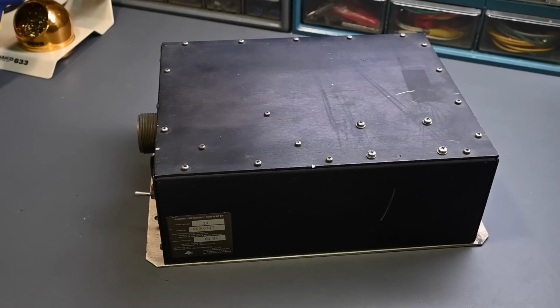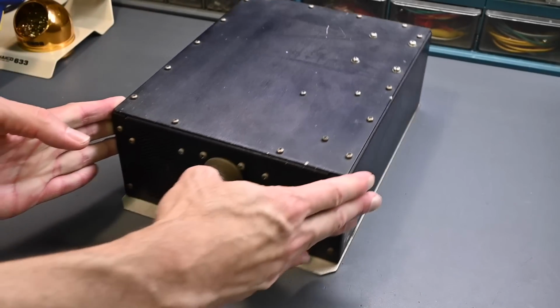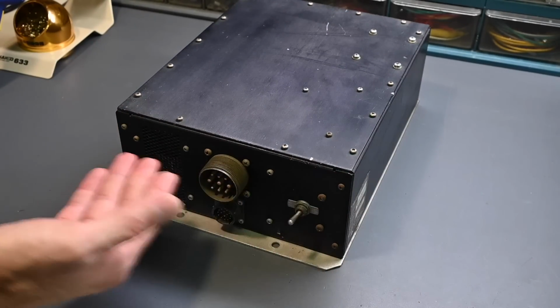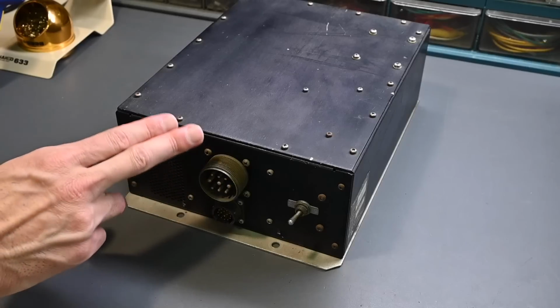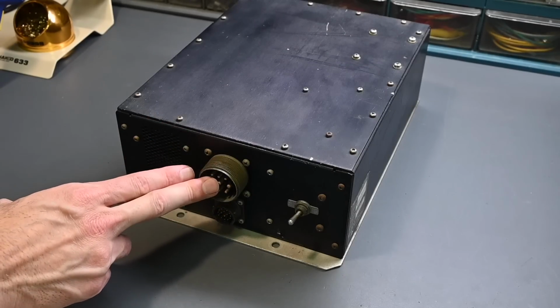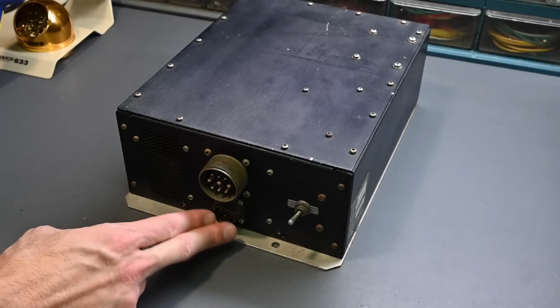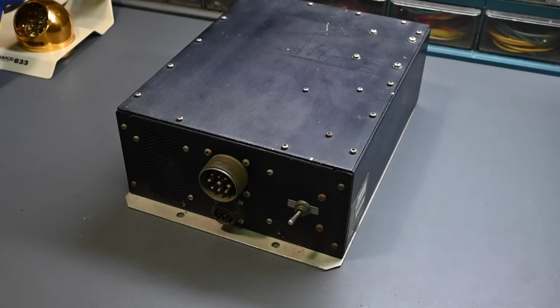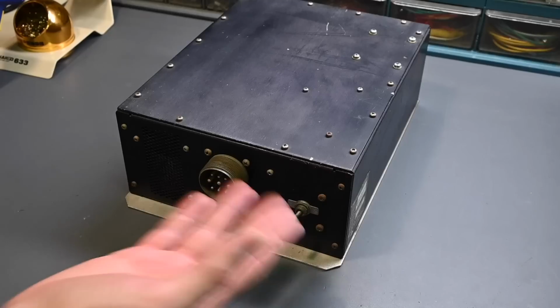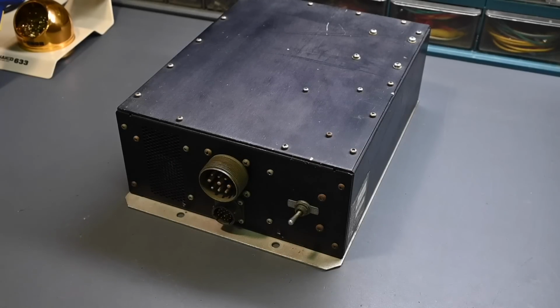I don't have any electrical connections or schematics for this frequency converter, so we'll have to take some resistance measurements on these connectors right here on the side panel, I guess you could call this the front of the converter. This larger connector looks like it would have the power in and out, and there's a smaller connector that might be for control, remote monitoring, or possibly even paralleling multiple converters to increase the total power capability. But we'll start with this connector first and see what it takes to just get power into the converter and try to power it up.